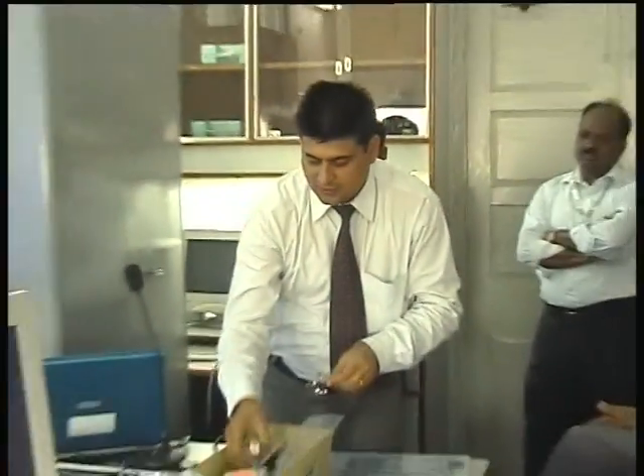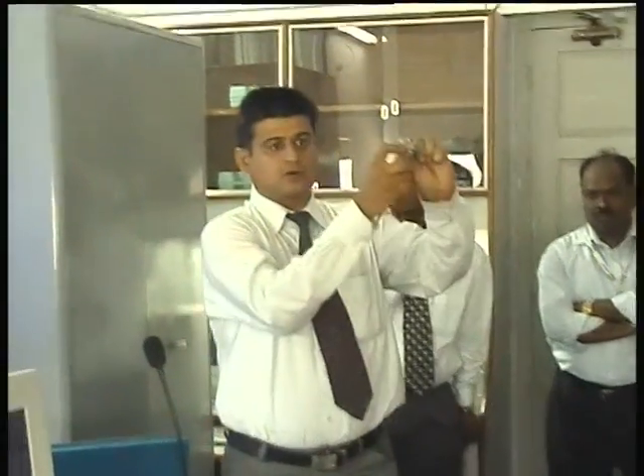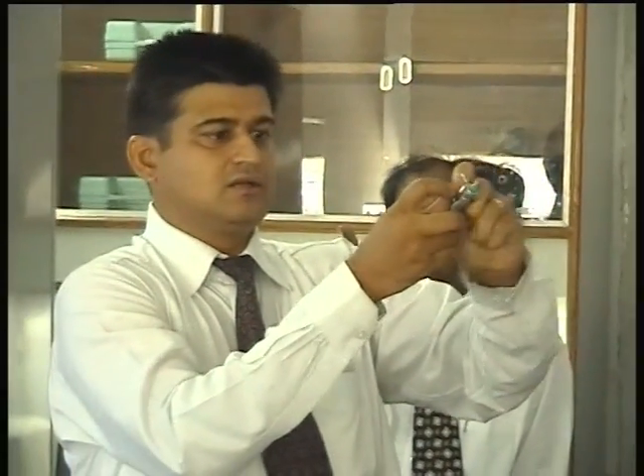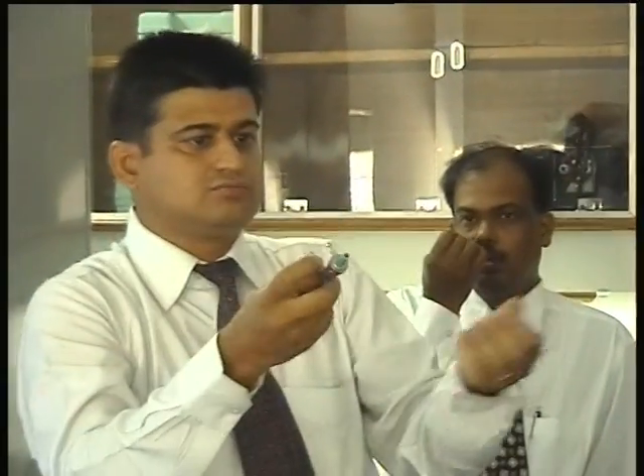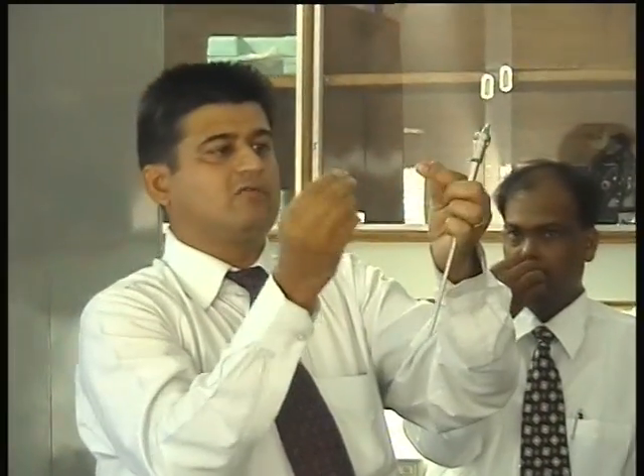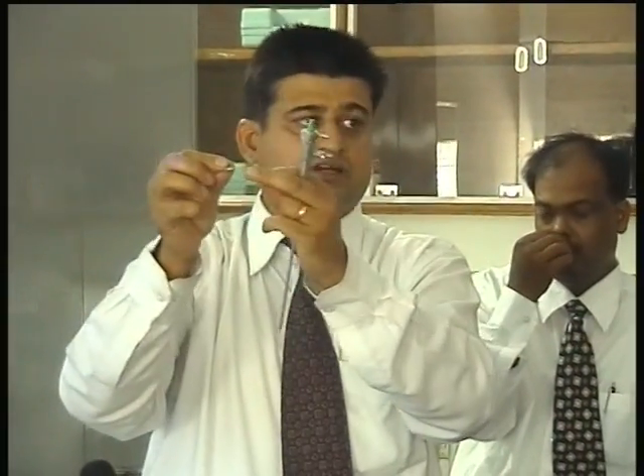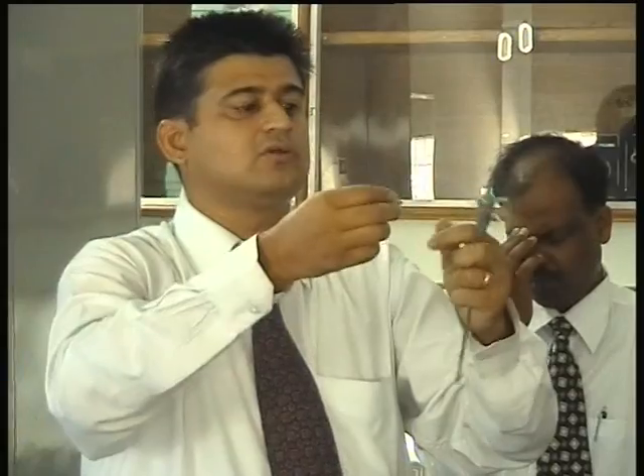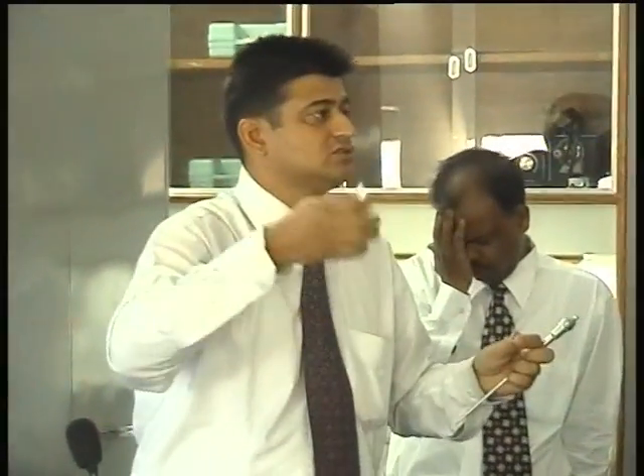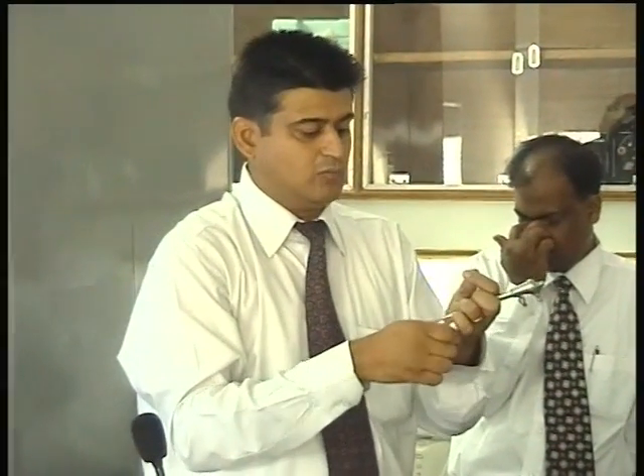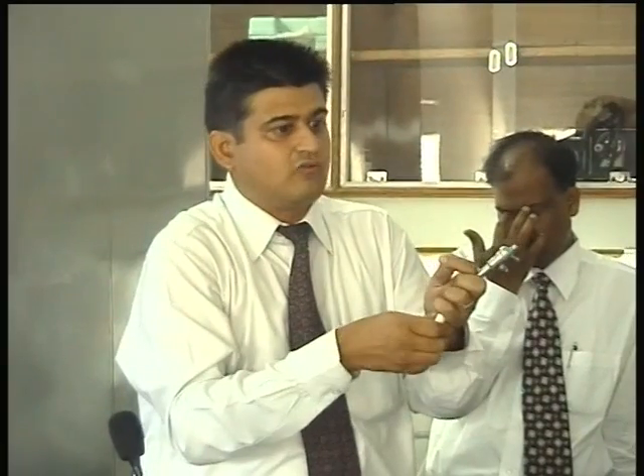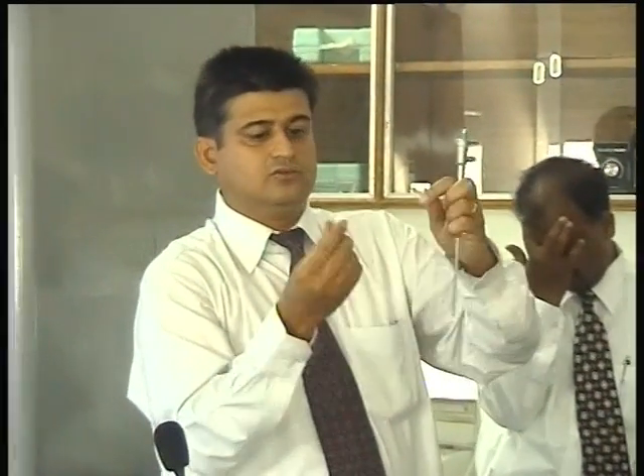Then there are something called luer locks. These are luer locks. We have a tendency to forget to open these because nobody told us, but we should always open and clean these. There are threadings which get worn out as a result because they have not been opened any time. Then there is a special grease, as we use grease on cycle chains, and it keeps it moving very finely. So we have a grease here for these stopcocks, and using these types of gadgets really enhances the life expectancy of your instrument.